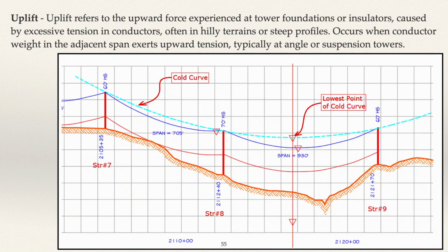Uplift. Uplift refers to the upward force experienced at tower foundations or insulators caused by excessive tension in conductors, often in hilly terrains or steep profiles. Occurs when conductor weight in the adjacent span exerts upward tension, typically at angle or suspension towers.